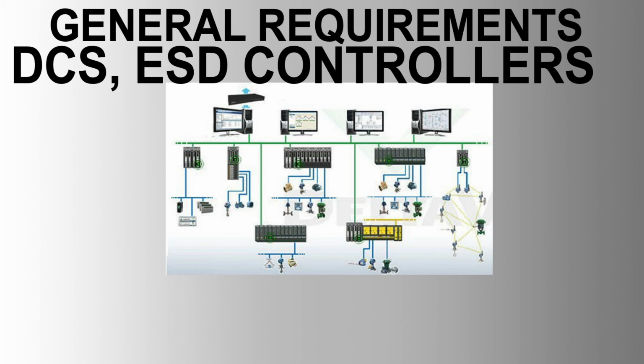6. Availability and redundancy. The design must ensure no single point of failure. The design should be 2 by 100% at all levels. All clients must be designed so that any local failure results in the loss of only one client. Each component of ESD must have dual redundant power supply modules. Automatic bumpless switchover for redundant components and communication links. Capability for global access by tag number to each process and calculated variable from any node.